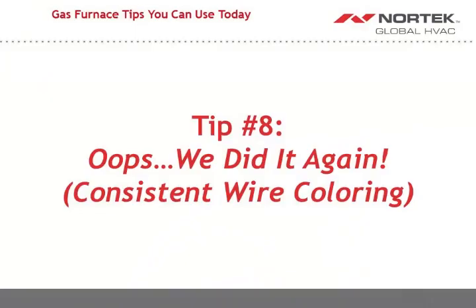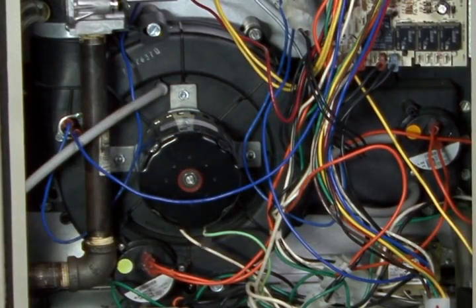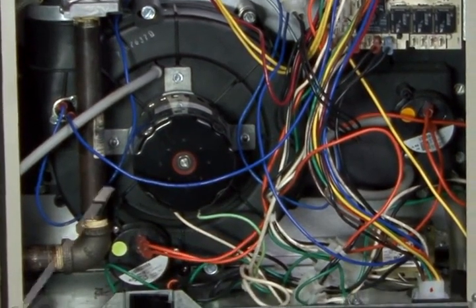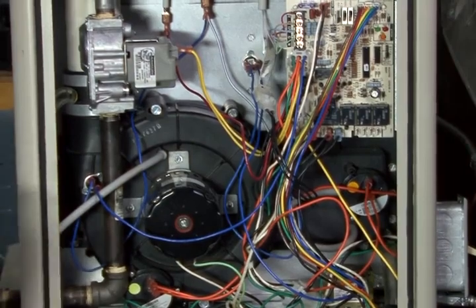Okay, tip number 8. I like to call this one, oops, we did it again. One of the things that I really like about our manufacturing and our brands, particularly when it comes to the gas furnaces, is that we consistently design and make the control circuits out of the same color of wires from one model to the next. As an example, on G6 models, the limit circuit was entirely made of blue wires, and the pressure switches would typically be in orange wires. If you look now at the G7 line, you'll see that we've got a limit circuit, and that's blue wires. We've got a pressure switch circuit here, and that's orange wires. We consistently do that over and over again from one model to the next.